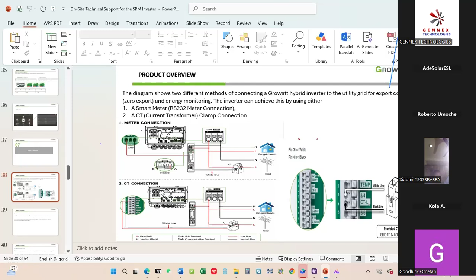I've talked about this one, so I'm finished. Then the parallel connection of this inverter. For the parallel connection, you configure the master, and the second as the slave. When it's in three-phase, we call it 3P2, 3P3. So for this inverter, you have to do the connection in this way: the first inverter is phase A, the second inverter is phase B, and the third inverter is phase C.